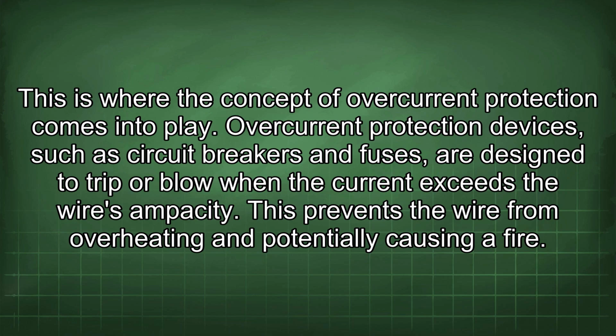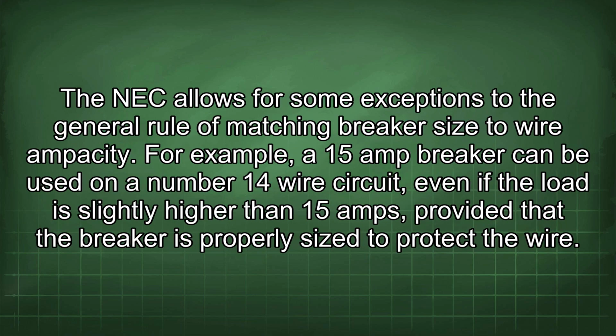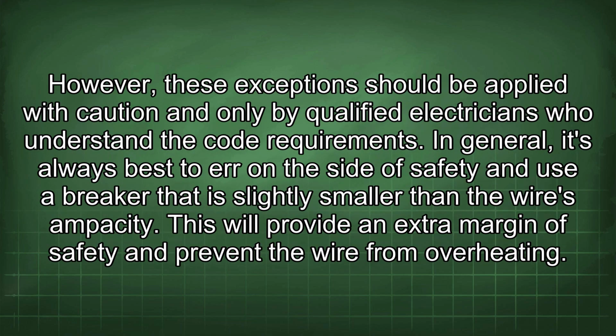This is where the concept of overcurrent protection comes into play. Overcurrent protection devices, such as circuit breakers and fuses, are designed to trip or blow when the current exceeds the wire's ampacity. This prevents the wire from overheating and potentially causing a fire. The NEC allows for some exceptions to the general rule of matching breaker size to wire ampacity. For example, a 15 amp breaker can be used on a number 14 wire circuit even if the load is slightly higher than 15 amps, provided that the breaker is properly sized to protect the wire. However, these exceptions should be applied with caution and only by qualified electricians who understand the code requirements.